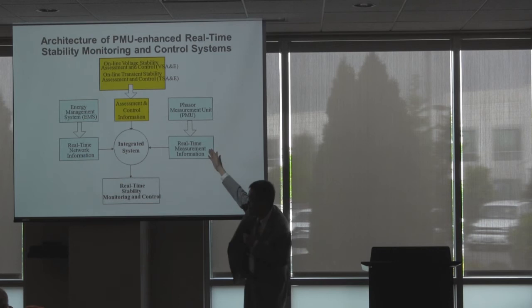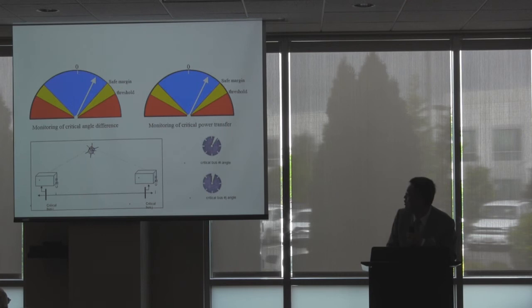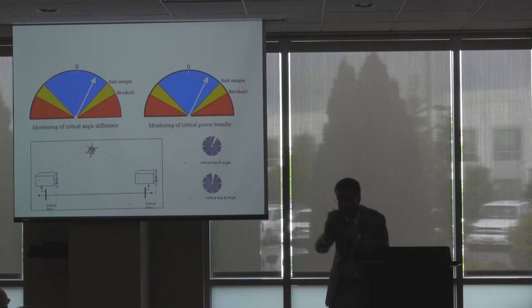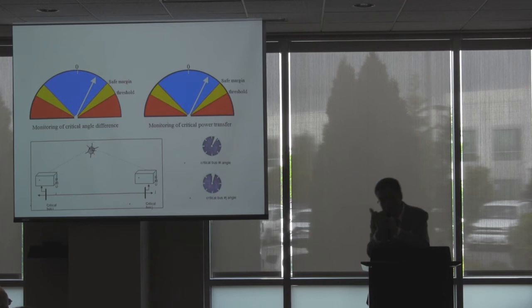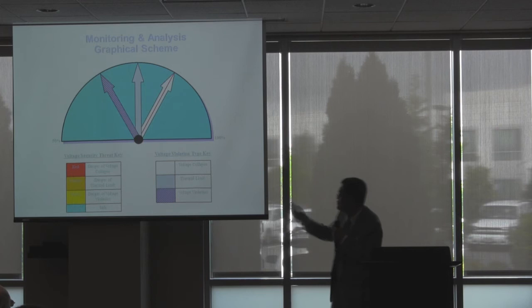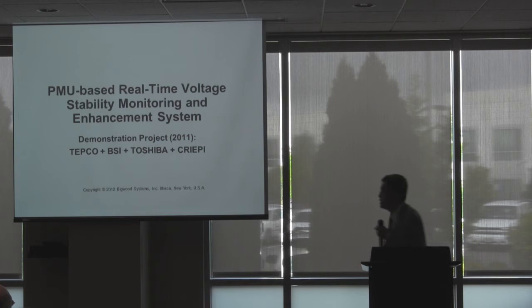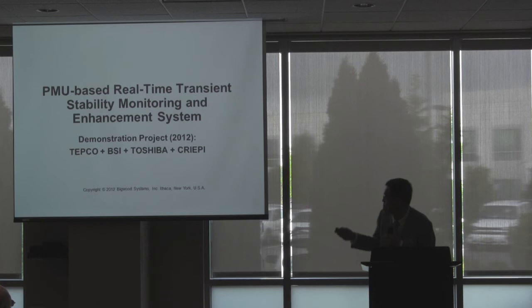My true belief is that with PMU providing real-time information — such as current line flow — combined with the EMS system providing the system model, and online computation providing assessment and control information, we should integrate these three pieces together. With the PMU we get the real-time needle values; the threshold values come from online computation. So you know where you are and where your limit is — that is your current margin, whether for voltage stability, thermal limit, voltage violation, or transient stability. We also did a project at Toshiba creating a PMU-based real-time voltage stability monitoring and enhancement system in 2011, and last year for transient stability monitoring and enhancement.